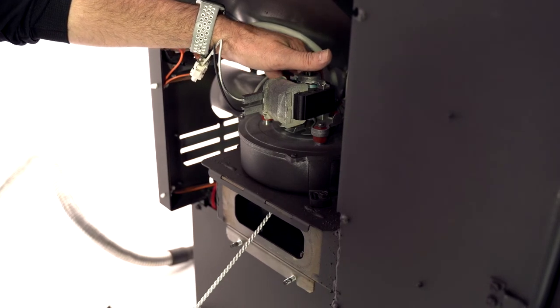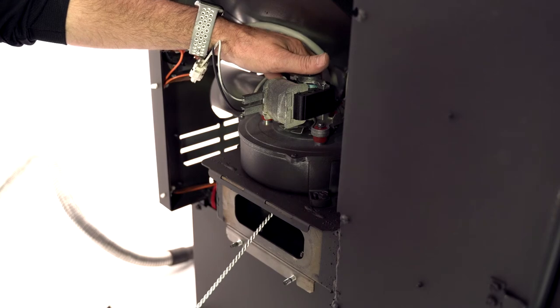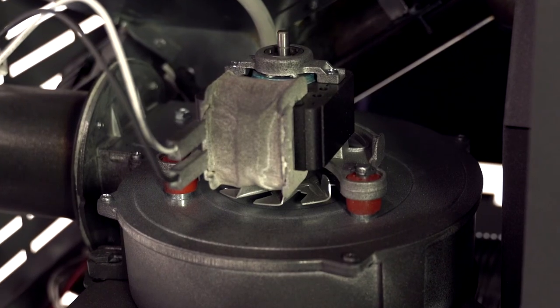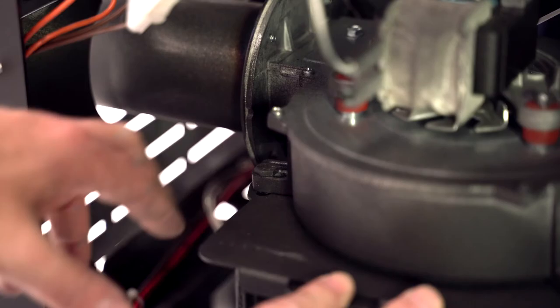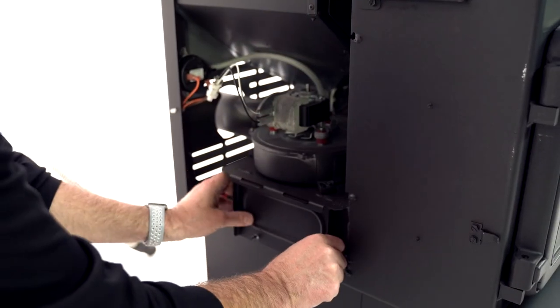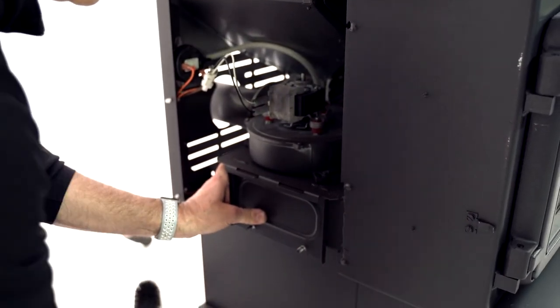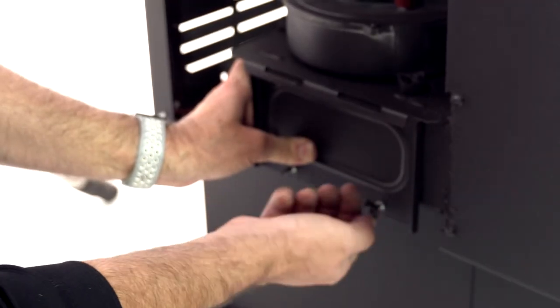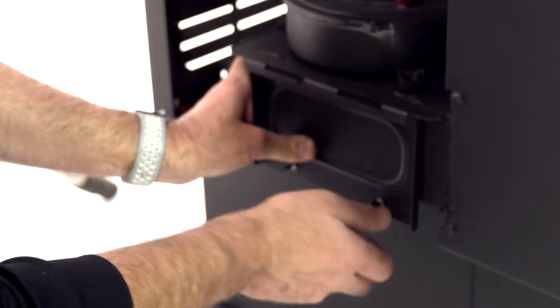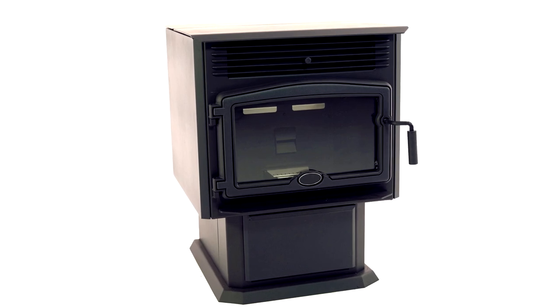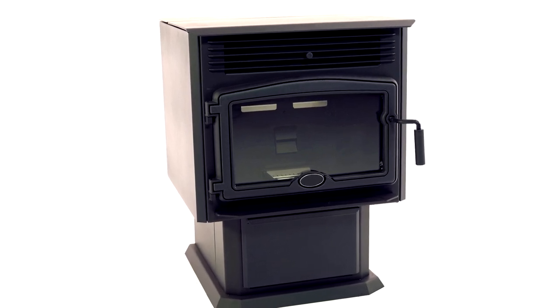During an annual maintenance, it is also possible to completely remove the exhaust fan assembly to facilitate the cleaning. It is held in place with three bolts around the fan. If you choose this procedure, consider replacing the gasket located between the fan and the exhaust channel. Once the channels have been cleaned, reinstall the left decorative panel.